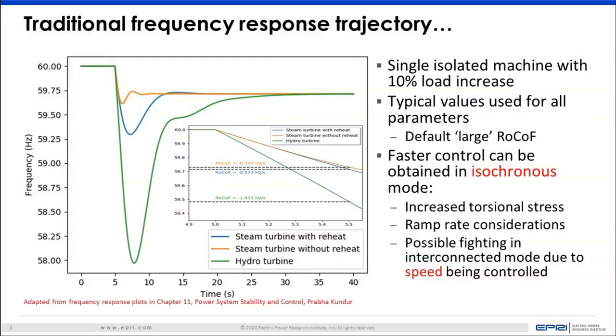You get 0.5 hertz per second or 1 hertz per second. By default, you get a large rocof in this isolated scenario. But what's more interesting is that you have this varied time constant behavior when compared across a hydro machine and a steam machine, with and without reheat. Now, of course, you can get faster control in isochronous mode instead of just regular droop control mode, but that results in increased torsional stress, or you can have ramp rate considerations.